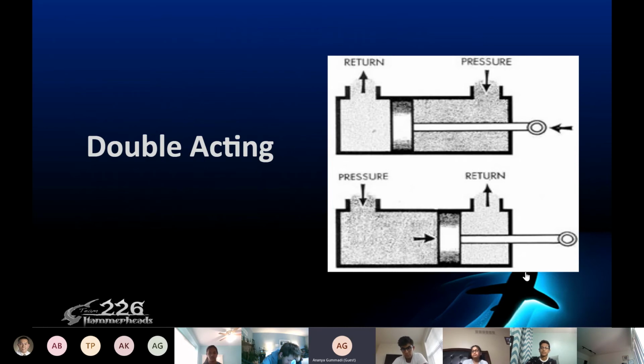It has two solenoids, and each one causes the sliding valve to move to one position or the other. So programming would need to create two solenoid objects in the code, one to apply air pressure to one side of the valve and one to apply air pressure to the other side. You only need to apply power to one side or the other to move the valve to that side.